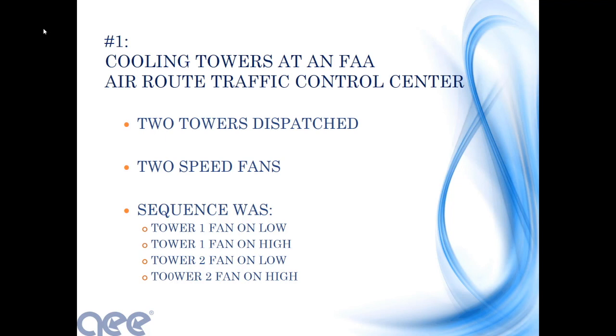And they had oversized condenser water pumps because they not only had to take the heat out of the chillers, they occasionally had to take heat away from the emergency generators that they operated. And even with only a single chiller online, they had 2 cooling towers dispatched. The cooling towers each had 2-speed fans. And the sequence that they set up was to have Tower 1 fan come on low, then go on high. If the condenser water continued to warm up, then they started the second tower fan, the fan on the second tower at low speed, and brought it up to high.